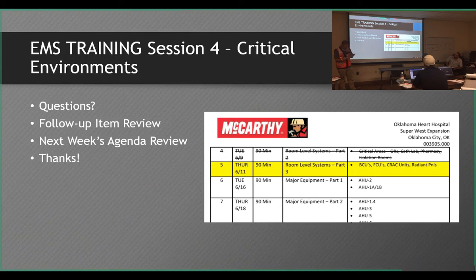The pharmacies, so we're going to send you a weekly trend for temperature, humidity, pressures, and air exchanges, similar to the other reports. We're going to add the air exchanges to the graphic. And we're going to do it for the pharmacy, ante, and 2 buffer rooms, right? So we can track that main pharmacy space as well. And then on the isolation room, we're just going to follow up to make sure that we never drop below the required air exchanges of 6 when we're in isolation.